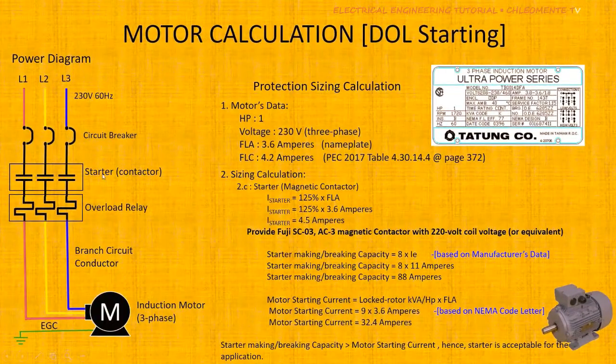For the magnetic starter or contactor, in practice the contactor is selected based on the HP rating of the motor, but applying a safety factor. Using 125% of the rated current, based on experience, sizing a contactor equal to the motor HP rating can cause contact wear over time during starting, because starting current is high and the contacts experience high current at every start.